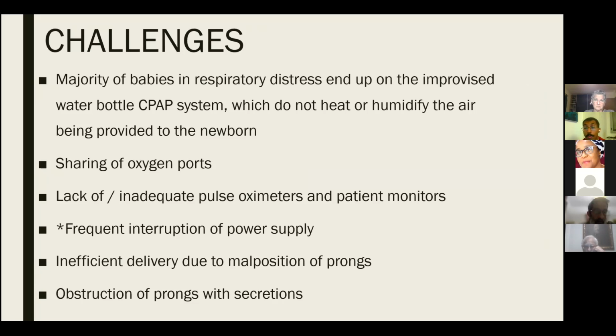Then there's the issue of sharing of oxygen ports. Sometimes we run out of oxygen ports. And because we're using a lot of the improvised water bottle system, it is difficult to tell how much oxygen we're giving. So because you have, say, 2 or 3 babies sharing one oxygen port, you want to be absolutely sure that the baby is getting enough oxygen. So we crank up the flow to the highest level, and we have no idea what is happening to the babies in the long term. Then lack of or inadequate pulse oximeters, like I mentioned earlier.